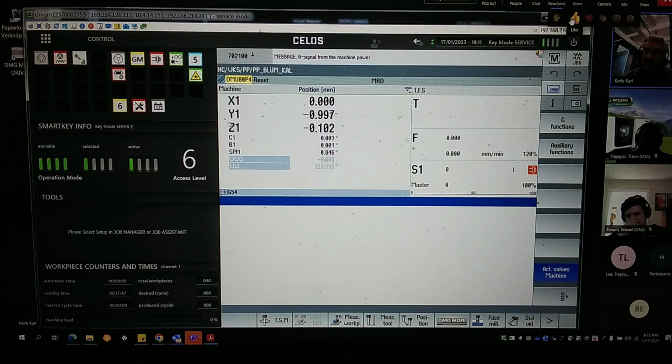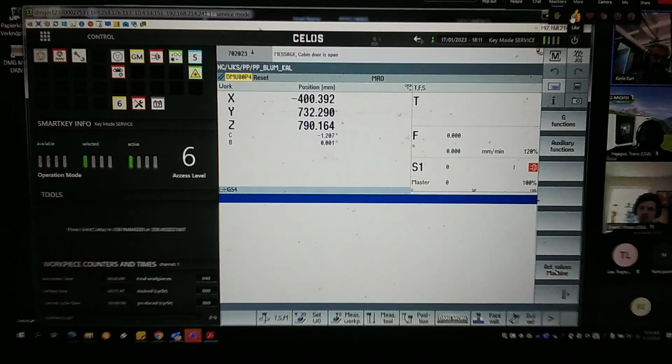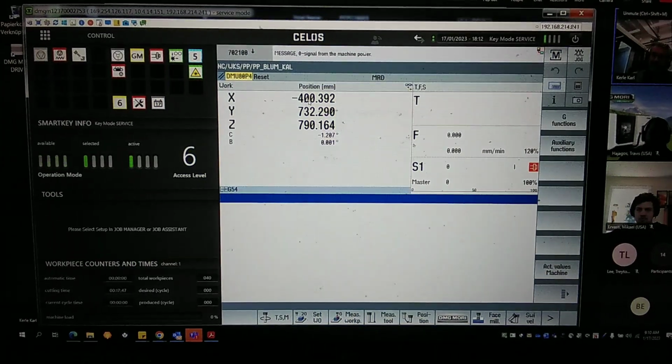Now it's highlighted, and look what happened. Do you see how big the position indication difference is? It's about 400-500 millimeters. Now we see where it comes from. These values, boys, are determined by a 0-point offset. It's not a help for us.